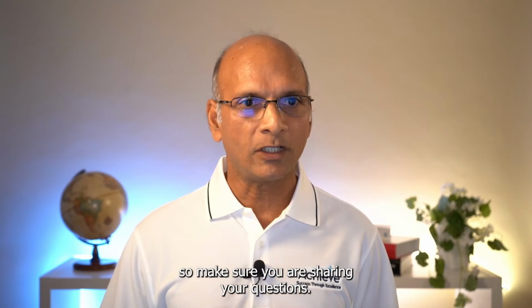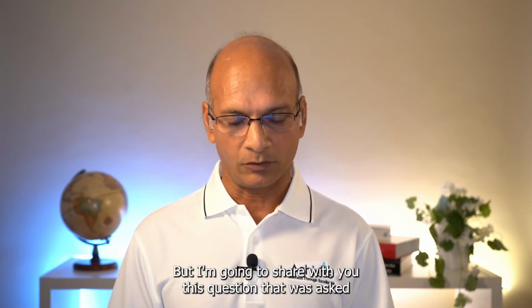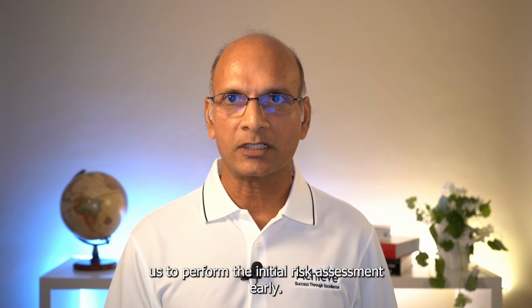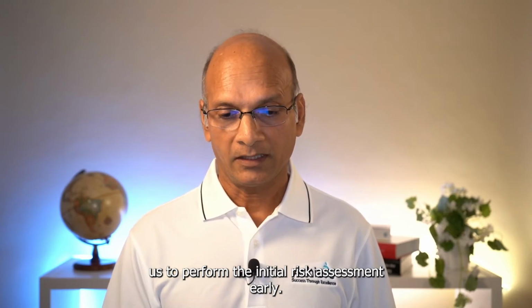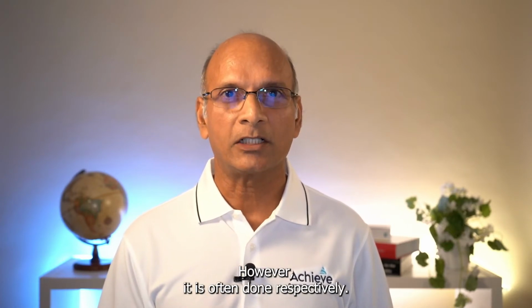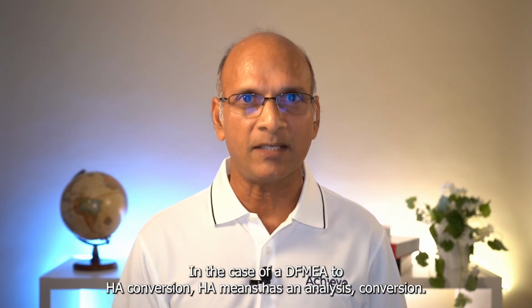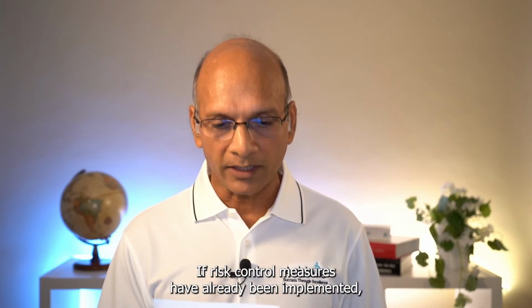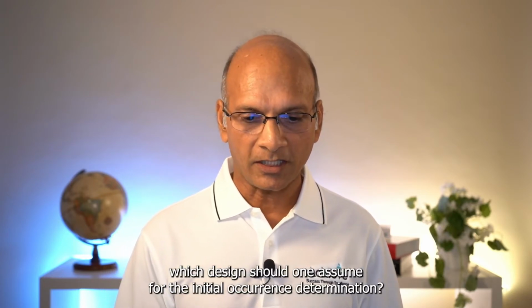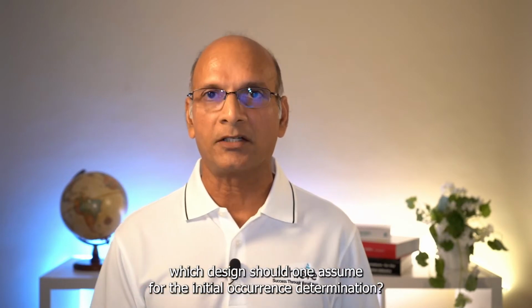Make sure you are sharing your questions, but I'm going to share with you this question that was asked at the time of registration. ISO 14971 asks us to perform the initial risk assessment early. However, it is often done retrospectively. In the case of a DFMEA to HA conversion, HA meaning hazard analysis conversion, if risk control measures have already been implemented, which design should one assume for the initial occurrence determination?